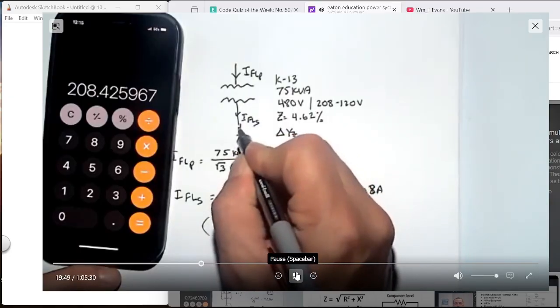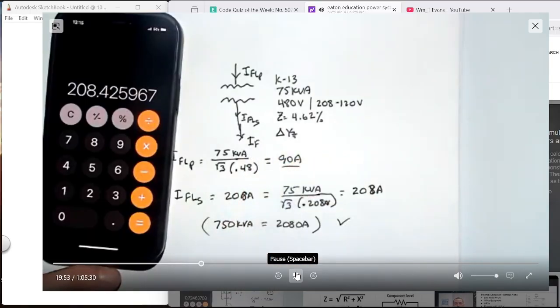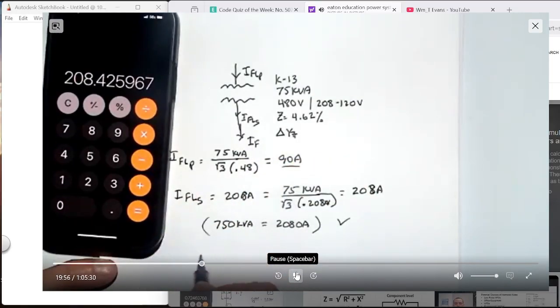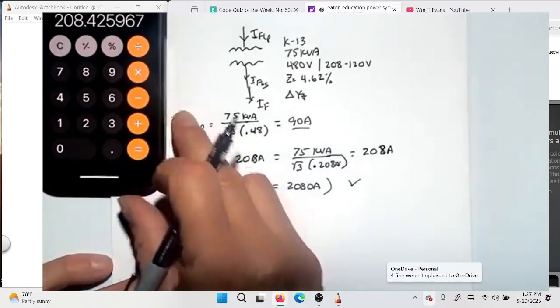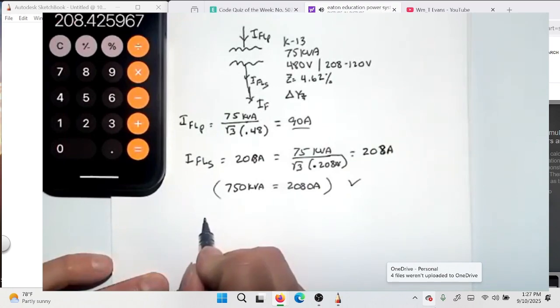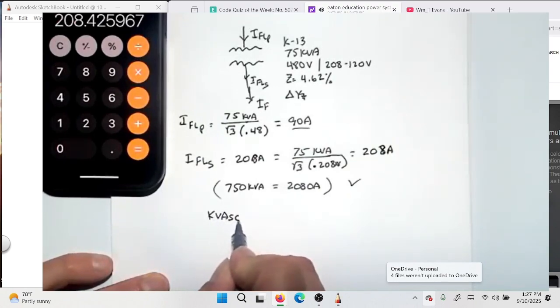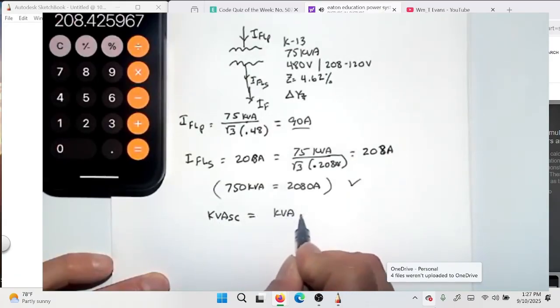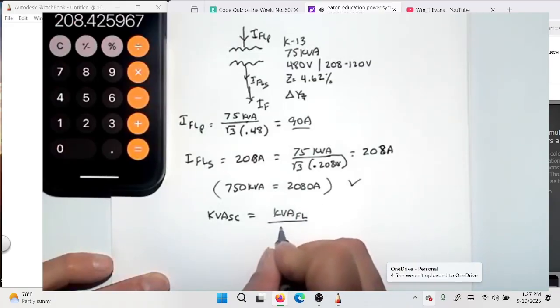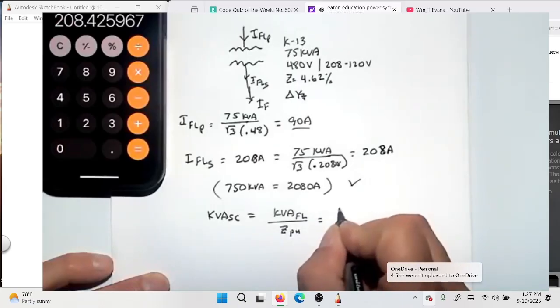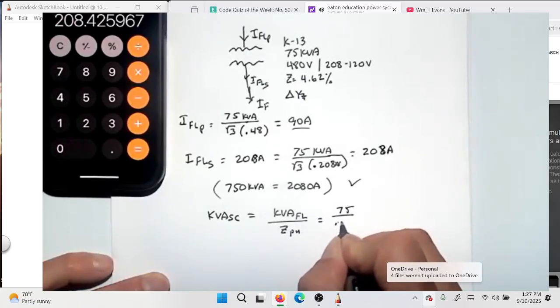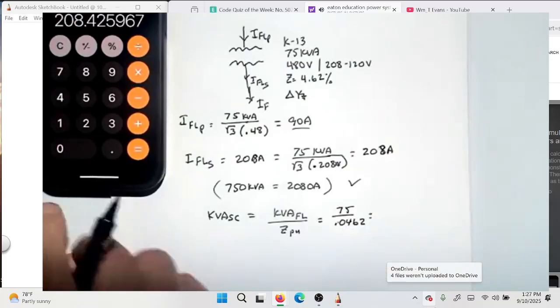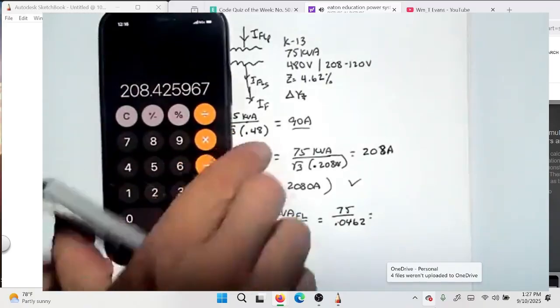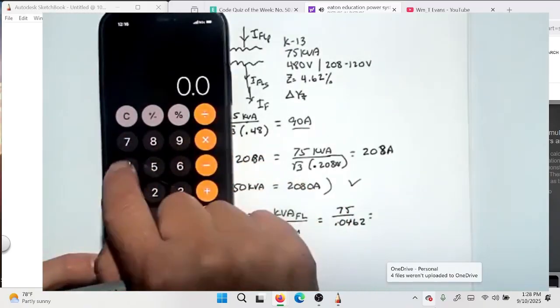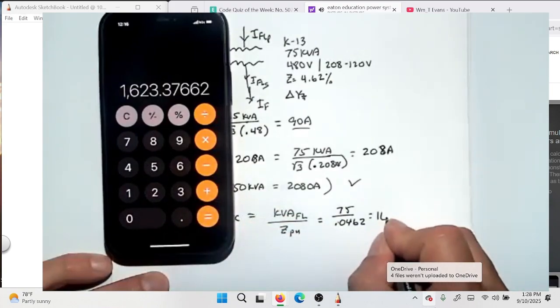What if I want to calculate my fault current, I fault? Earlier I mentioned we just divide the full load amps by the impedance, but really what we're doing is calculating kVA short circuit. kVA short circuit is kVA full load, which is our rating, divided by the impedance in per unit. So in this case it's 75 divided by 0.0462, which is 1623 kVA.